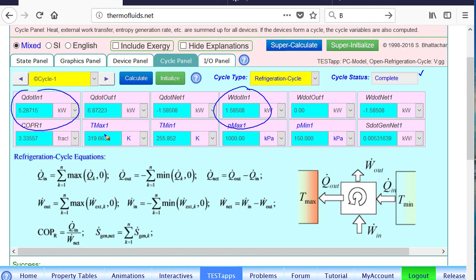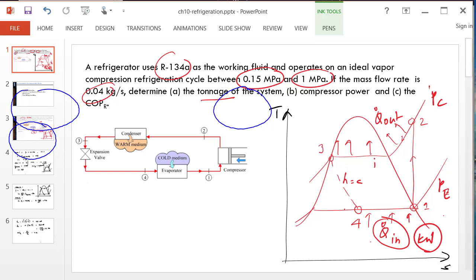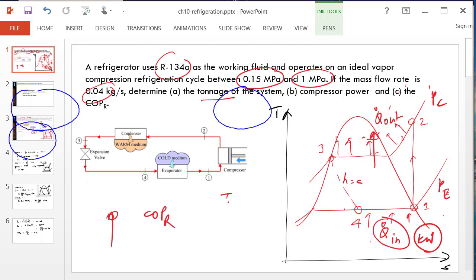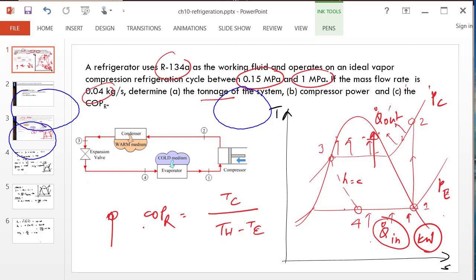More importantly, what is the COP? The COP is 3.33 for this particular cycle. Suppose we increase the condenser temperature: from the Carnot analysis, COP should go down if the difference between the cold and hot temperatures increases. The Carnot COP for a refrigeration system is TC divided by (TH minus TC). Even though this is not a Carnot system, increasing the difference between TH and TC means we expect the COP to go down.